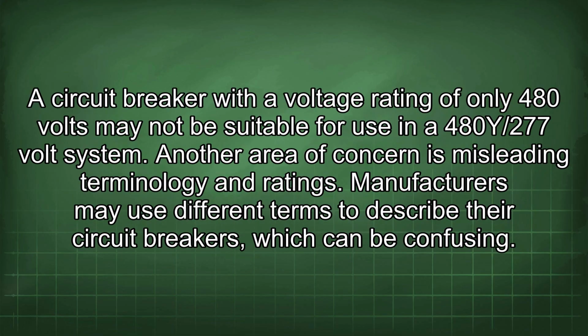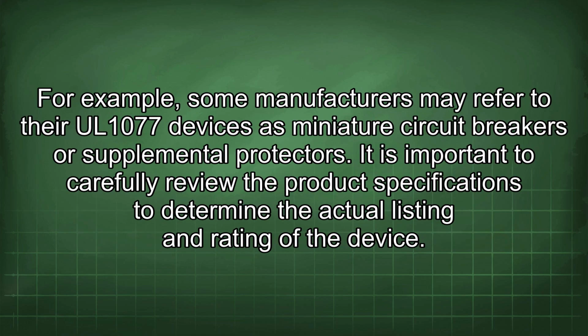A circuit breaker with a voltage rating of only 480 volts may not be suitable for use in a 480Y/277 volt system. Another area of concern is misleading terminology and ratings. Manufacturers may use different terms to describe their circuit breakers, which can be confusing. For example, some manufacturers may refer to their UL1077 devices as miniature circuit breakers or supplemental protectors. It is important to carefully review the product specifications to determine the actual listing and rating of the device.